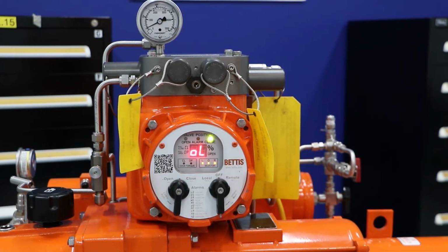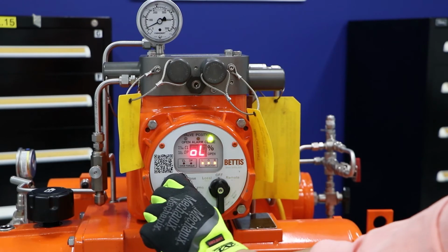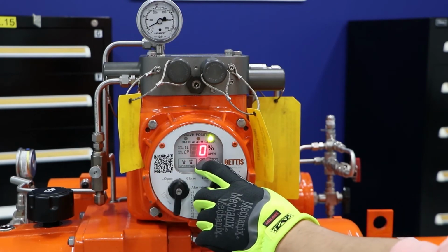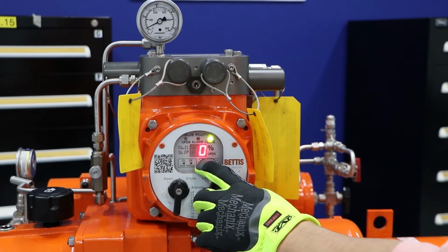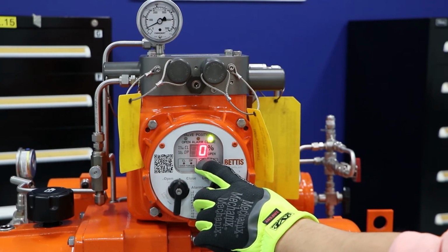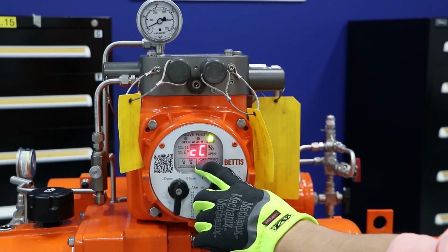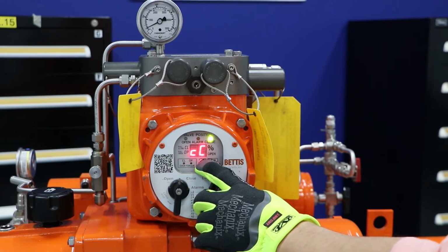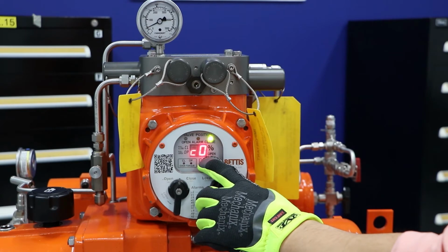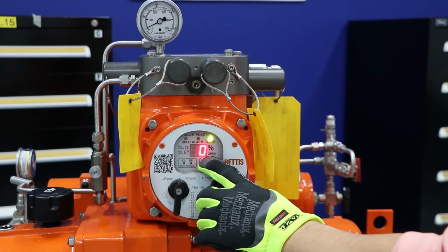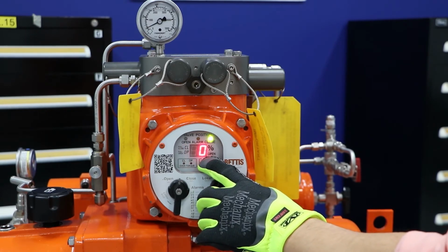OL. OL is analog output lower limit. In this case, this would be 4 milliamps. In order for us to calibrate this, we need to hit yes. Next, you'll see CC. CC is calibration choice. Calibration choice helps you determine if you want to increase or decrease the value. If it's 0, that means we want to increase the value. If it's 1, we want to decrease the value.